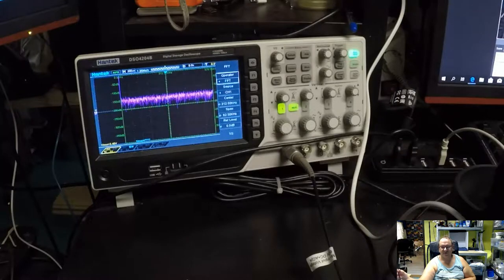If there is interference, it would need to destroy the whole digital protocol signal, and that's actually harder to do than screwing up an analog signal. An analog signal can be much more easily affected. That's why most sensors have moved to being digital at this point, and you can put in error checking and correction directly there. You can put protocol checking, you can put diagnostics on the sensor. It can be a smart sensor.